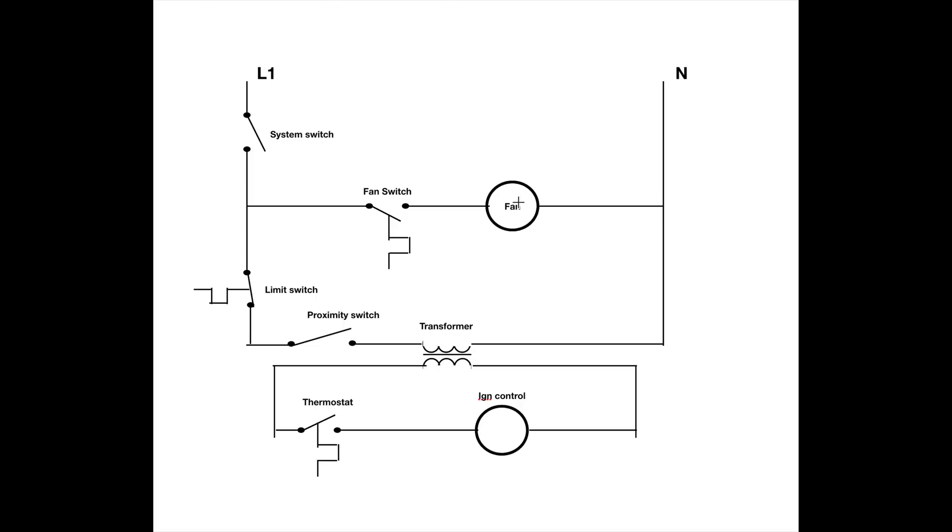So let's say I leave the area. After about five minutes, this proximity switch is going to open up. Now, all it does, it actually does the same thing as the limit switch does. It opens up the circuit to the transformer so that the ignition control shuts down and the burners go off. The fan continues to run because you want to clear the heat out of the heat exchanger. If I put this proximity switch, say, somewhere up here, then it would shut off the fan. So you put it downstream of the fan.